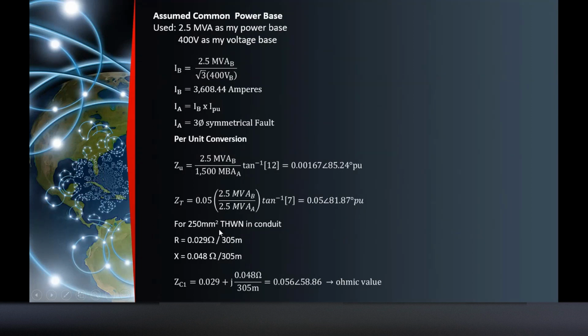For 250 mm square THWN in conduit, you will get the resistance and reactance values in the PEC, the Philippine Electrical Code. I forgot the table, but you will get there the resistance and reactance values of 250 mm square per 305 meters. So convert this to get the impedance. When you convert this to impedance and make it polar, 0.056 angle 58.86, which is the ohmic value of that particular cable. Since this is ohmic, convert it to per unit.